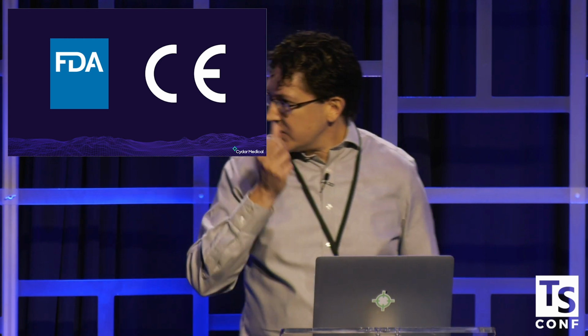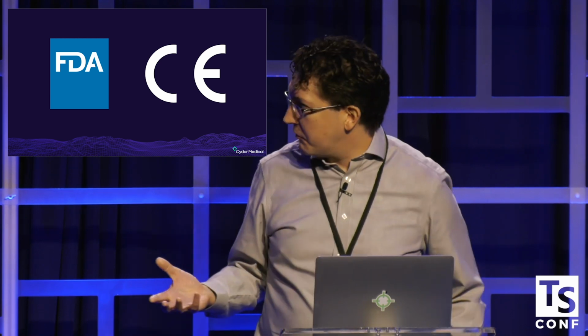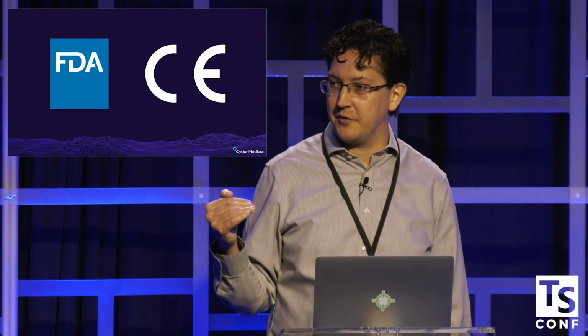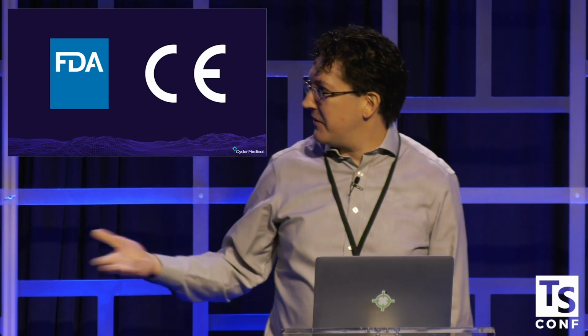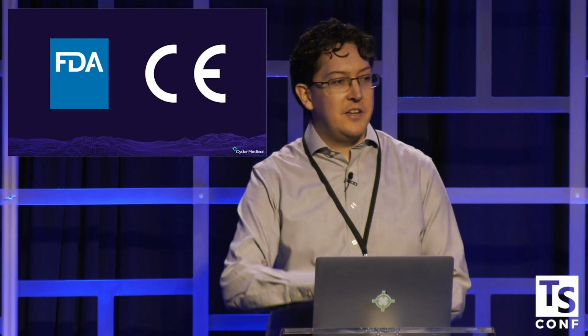The regulators are starting to get up to speed with the idea that you can have a medical device which is purely software. This is a relatively new thing. For a while, we were working from a checklist from 1997. Every time we had a release, we had to ask, does this change the sterility of the product? Well, you can't really sterilize software, so no. There's now a different set of checks if you've got a purely software medical device.